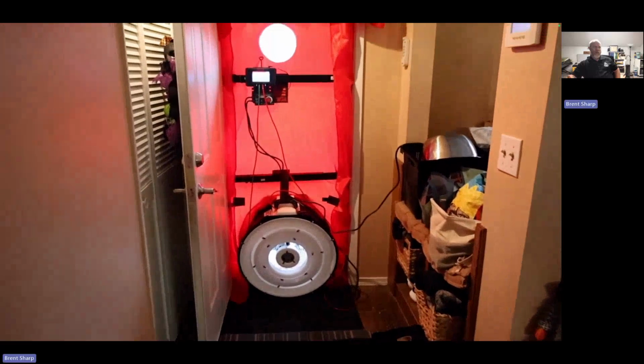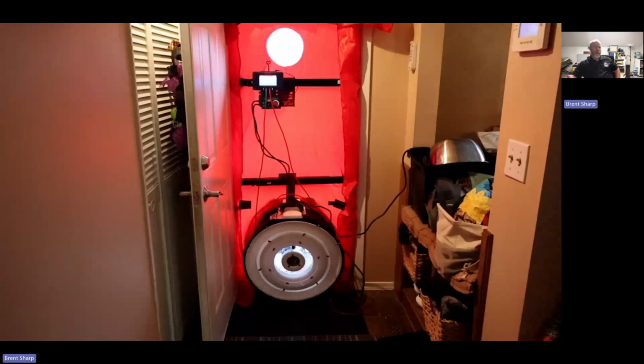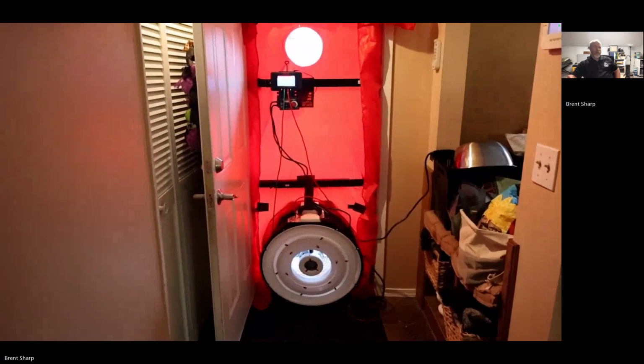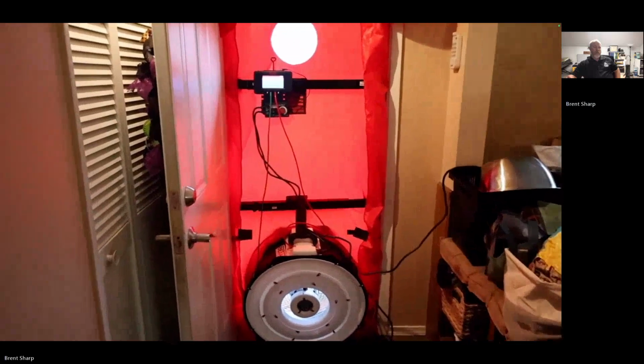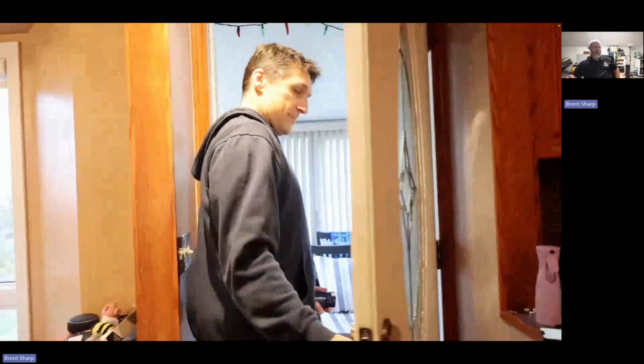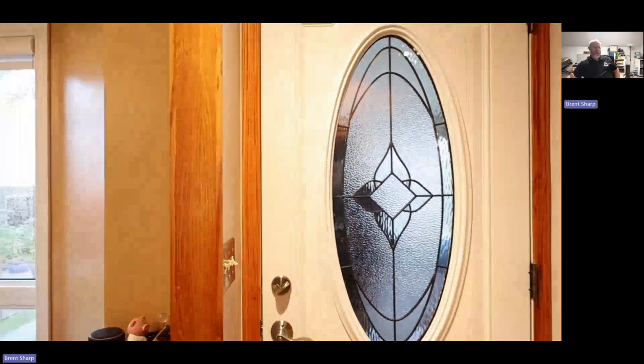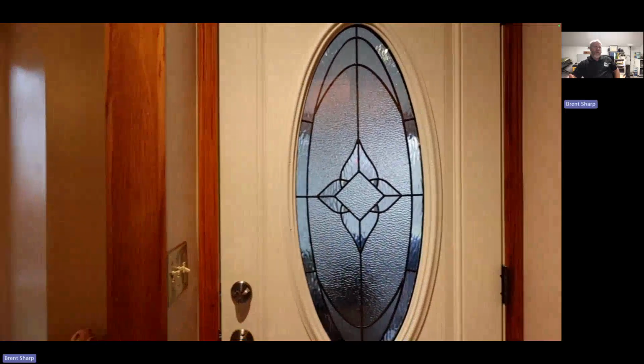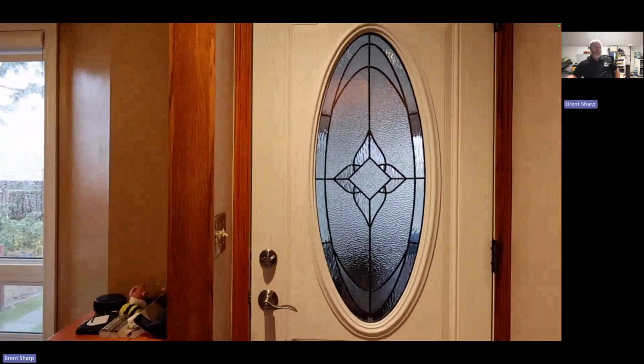As you can see here, we're just collecting our data on this. And we have to let it go through its series. This whole thing takes about 2.5 hours. So we did 2 tests, and we found out he had 2.5 changes per hour.